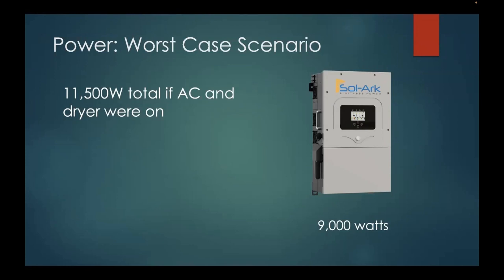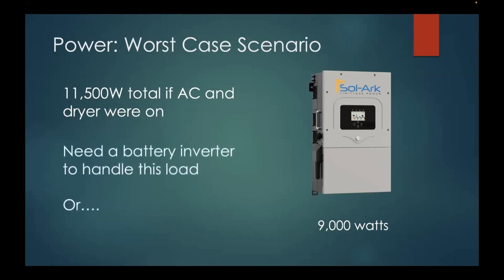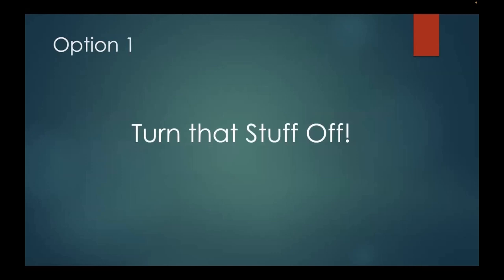But let's say I'm one of those people who doesn't care — I want the worst case scenario. I'm throwing a party, it's Christmas dinner, everything's going, I'm not grilling outside because it's cold, and I've got a whole house full of people. Fine, let's do that. So we need a battery inverter or two to handle this load — 9,000 watts is not sufficient. Okie dokie, then you're going to need two of them. Or what else can we do? Turn that stuff off.